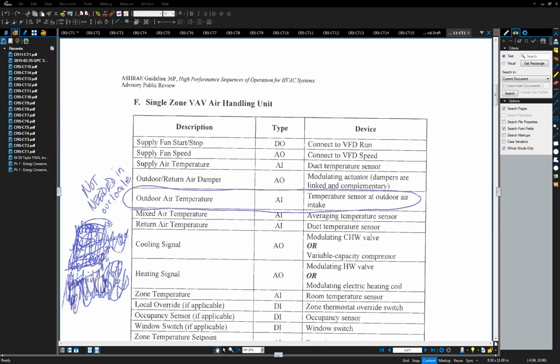Okay, so this was a temperature sensor at outdoor air intake, and it looked to me like it was saying that you're choosing the outdoor air sensor closest to the unit, which if you have them, that's fine. But what we do is we have a master station that we keep calibrated, and then we share that amongst our fan systems, our buildings. And so for us to have sensors in each air intake, we have a lot of fan systems at U of M, so it could be $1.5 to $2 million worth of sensors if we had adopted this over that period of time that we installed those systems. So we didn't think it should be prescribed that you have to have an outside air sensor in each outside air intake of each fan system.